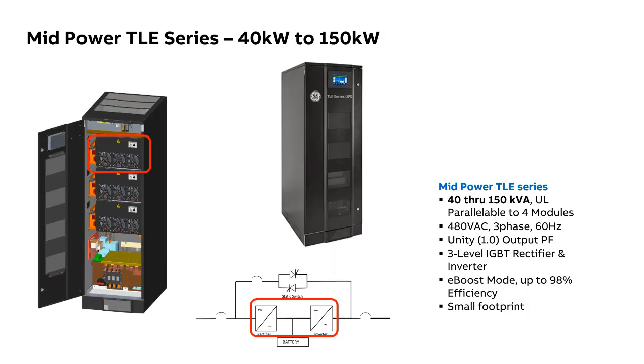Like all manufacturers in the industry today are doing it like this. They're building monolithic UPSs like this. And of course, it's a matter of volume of scale manufacturing wise. You build one power module, in this case a 50 kW, and then you build frames that can take a number of that 50 kW. You bolt them in, and then it's not meant to be a modular or scalable product. You close the door, and this is a 150 kW UPS, and that's what it knows. That's what it can do.